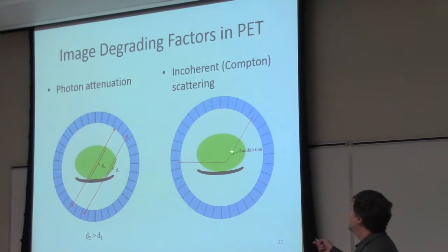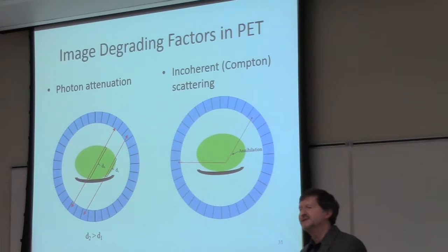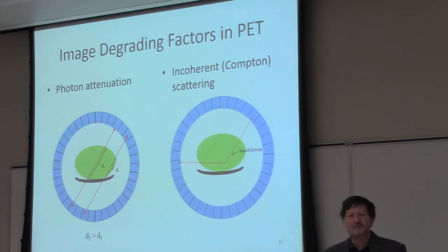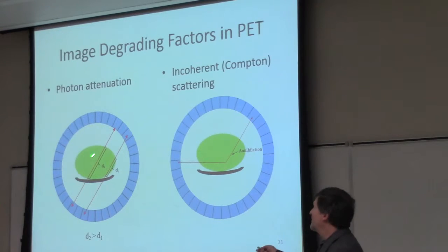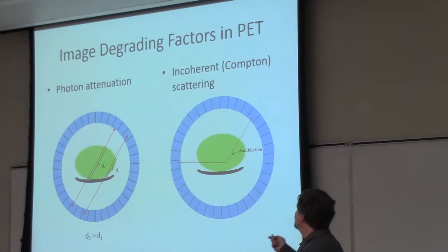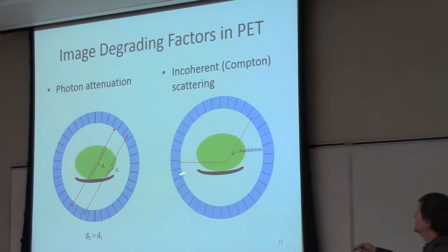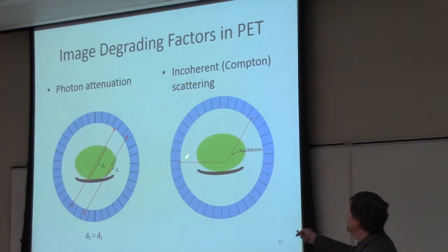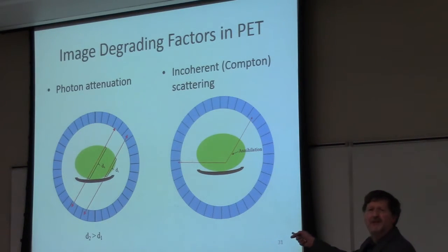We detect the two coincident photons and use this to reconstruct our image in a very similar way to CT — we create a sinogram, we do a back projection approach, and everything is corrected. However, there are two problems with PET. The first is photon attenuation — we have no idea of the anatomy, only the radiotracer uptake. That's not an anatomical image; it doesn't tell me anything about the anatomy, yet somehow I have to find a way of correcting for the photons produced. The other problem is scatter, and these two things get tied together because scatter is one of the interaction processes that takes place. At 511 keV in soft tissue, it's the most important interaction process — they are to some degree the opposite sides of the same coin.